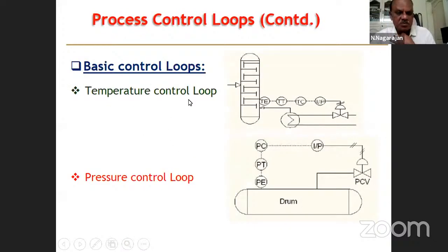Similarly, in a distillation column you have a temperature control loop. You want to maintain the temperature inside the column, and you measure the temperature here. You have a temperature element, a temperature transmitter, then it goes to the controller. Control signal is converted from electronic to pneumatic, because finally the valve will be operated by instrument air. Okay, so these are the elements: measuring element, transmitter, controller, and the IP converter. Okay, electronic to pneumatic converter, which finally acts on the steam inlet to the reboiler.